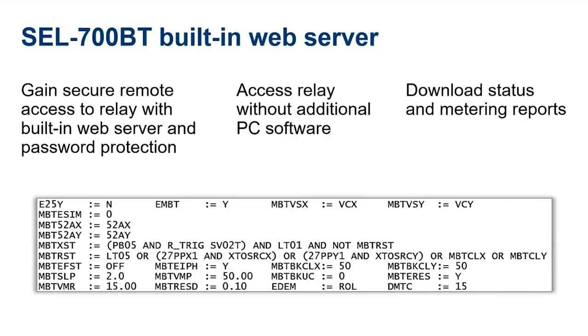SEL700BT includes a web server. With the web server, you can access basic device information on a standard Ethernet network with the built-in web server in the product. You can interface with the relay with any standard web browser to perform the following functions. You can log on with your password protection, safely read relay settings, verify relay self-test status, and read relay configuration. You can inspect meter reports. You can download event history, event reports, sequential event recorder, SER data, all this from your desk using the web server.